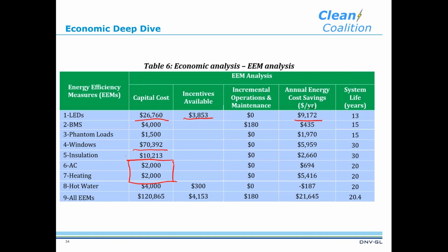For an extra cost—what we have here is $2,000 to be conservative, but it's probably closer to $400 per unit—you can switch that to a heat pump, which basically adds a reversing valve and uses the air conditioner to run backward, vastly increasing efficiency. But you have to know that's what you want when you order it, otherwise they're not going to help you. For building owners, the lesson here is to be really prepared for when a replacement's coming, so you get what you actually want and don't miss a really good opportunity to install high efficiency equipment at low cost, because you only get that chance every 20 years.